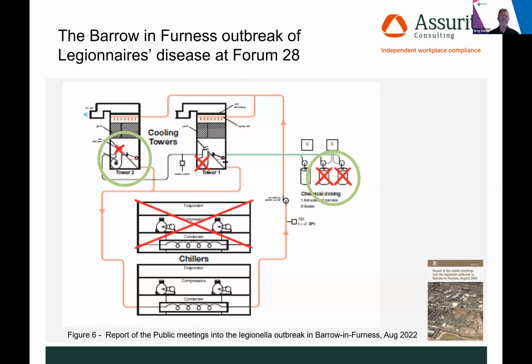Cooling tower number 2: the fan damper on one of the internal fans had become so badly corroded it was stuck shut in the closed position and couldn't be opened.